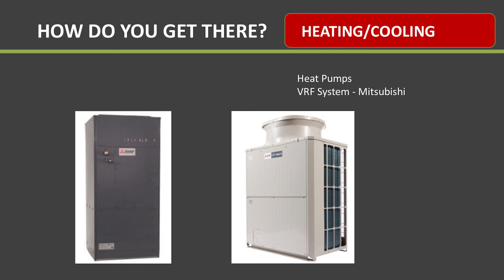Make sure you're designing these for the reduced loads you'll have because of such an efficient envelope. These are also electric systems, which we've been talking about to be more efficient on the grid. So heating and cooling use individual heat pumps in each unit, on a VRF system, meaning each unit has its own in-unit equipment, but the condensers on the roof are grouped, which also saves lots of space on the roof. It's a more efficient system that can simultaneously heat and cool across the building.